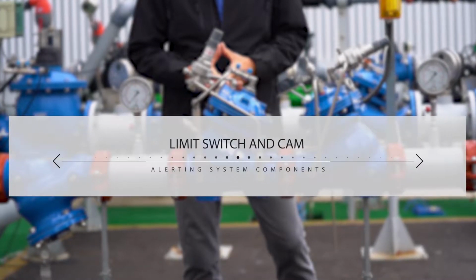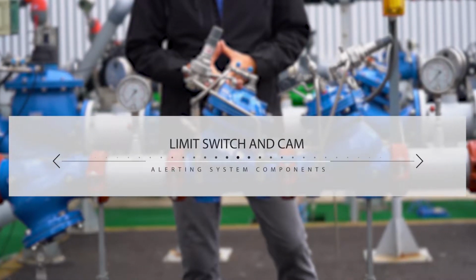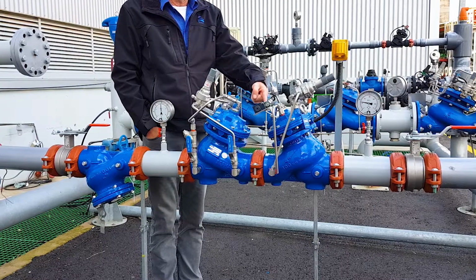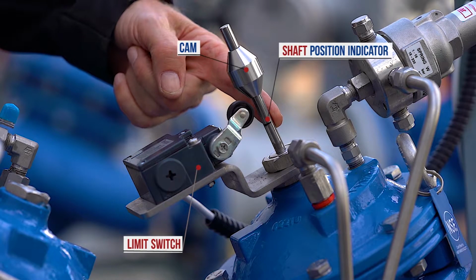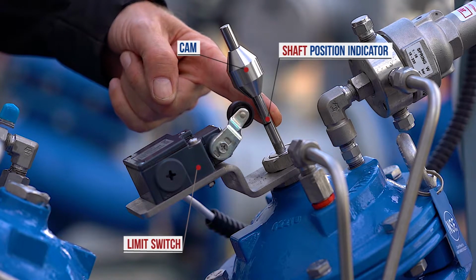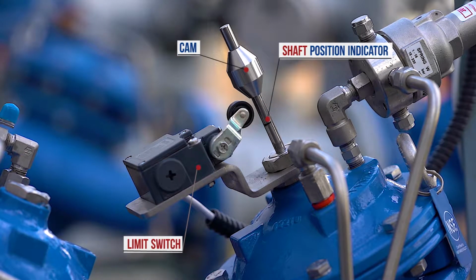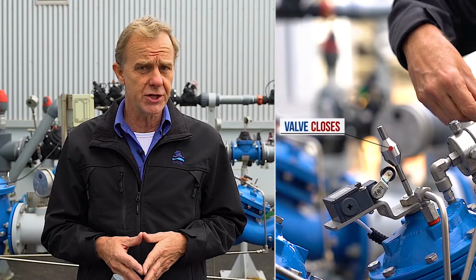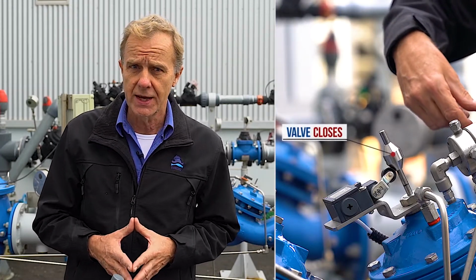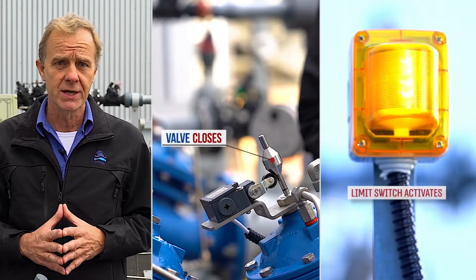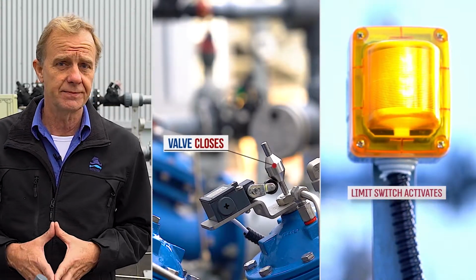Before moving on to maintenance, I'd like to explain a few things about the limit switch and the cam, which are part of the alerting system of this station. The limit switch and the cam are attached to the shutoff valve's main shaft and are both calibrated at the factory. Rarely should they require readjustment. The switch retains its idle circuit connection as long as the pressure level has not reached the emergency level, which means the emergency shutoff valve is fully open. If the emergency pressure level is reached, the emergency valve starts to close, and the limit switch alerts the building management system so responsible authorities can take action.